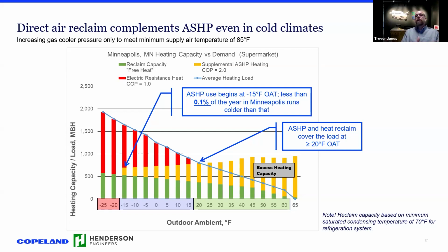But at the very cold temperatures, when you're doing direct reclaim, you end up getting more of the heat more easily, where the temperature of the refrigerant is enough that you're boosting your outside air. Typically, that is the biggest portion of the load through the air handlers, the rooftop units. So bringing that up to temperature is easier when it's really cold with the direct reclaim. And as our reclaim falls off as the air becomes warmer, we see that air source heat pumps cover more and more of the load.